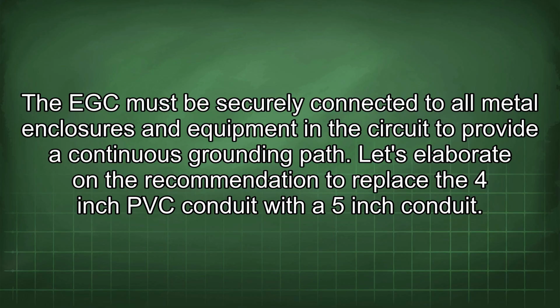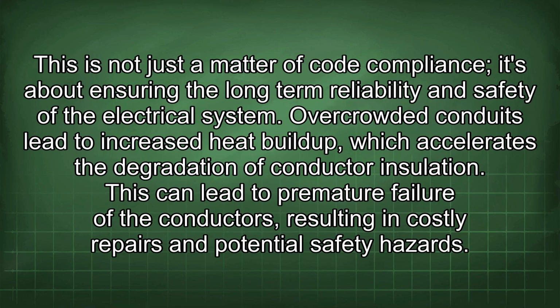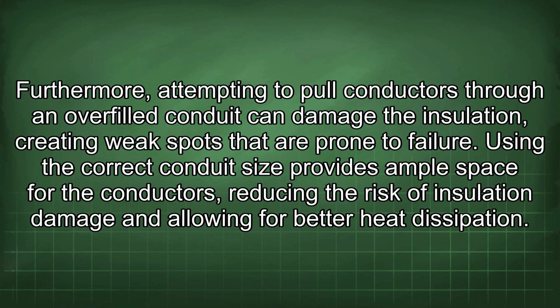Let's elaborate on the recommendation to replace the 4-inch PVC conduit with a 5-inch conduit. This is not just a matter of code compliance, it's about ensuring the long-term reliability and safety of the electrical system. Overcrowded conduits lead to increased heat buildup, which accelerates the degradation of conductor insulation. This can lead to premature failure of the conductors, resulting in costly repairs and potential safety hazards. Furthermore, attempting to pull conductors through an overfilled conduit can damage the insulation, creating weak spots that are prone to failure. Using the correct conduit size provides ample space for the conductors, reducing the risk of insulation damage and allowing for better heat dissipation.